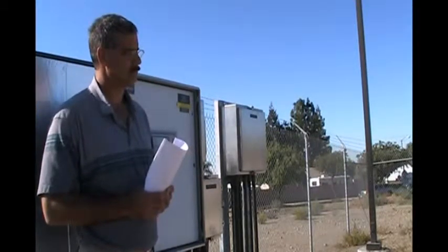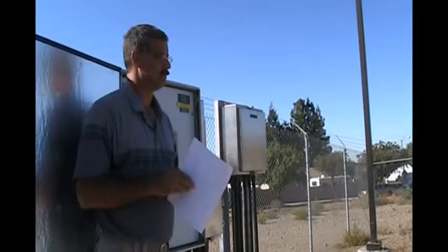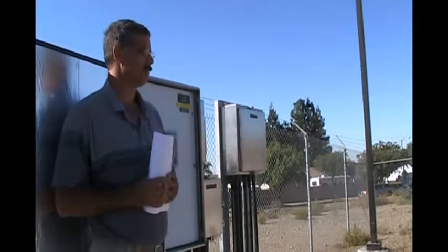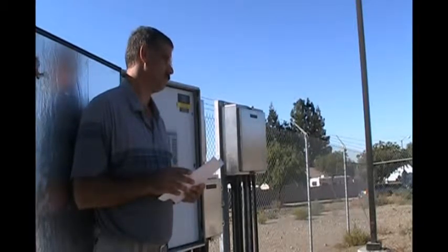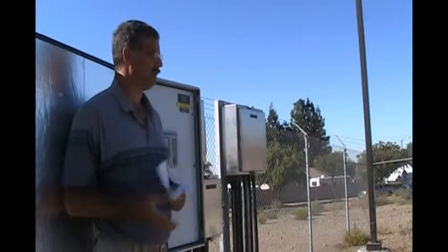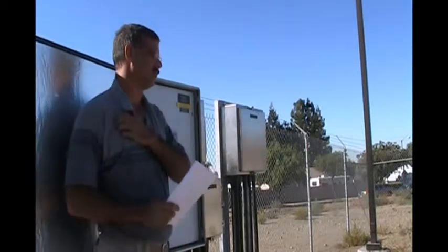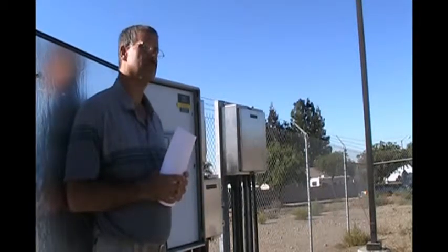I noticed some of these screens show 30.00 CFS or 13.00. Another place is 13.0. Those are made up numbers just for the manual. Can you help? If you put in 13.00, is this valve going to open and close based on the pressure here 5,000 times a minute or what? Well, if the pressure drops below 60, it will close down. Once the pressure returns, it will try to go ahead and operate again as normal. I just want to try to find out what's normal. It's like constantly seeking. Is that what that's Yeah.